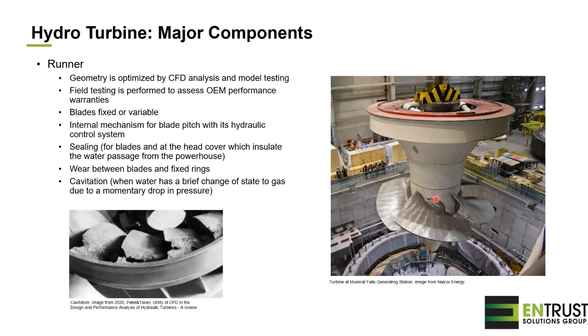So more and more the technology is to go from oil-filled runners to air-filled, just compressed air, to prevent oil from going into the water of the river. We will eventually find wear between the blades, the blade tip, for example, and the fixed rings. So that will be important to investigate over time.